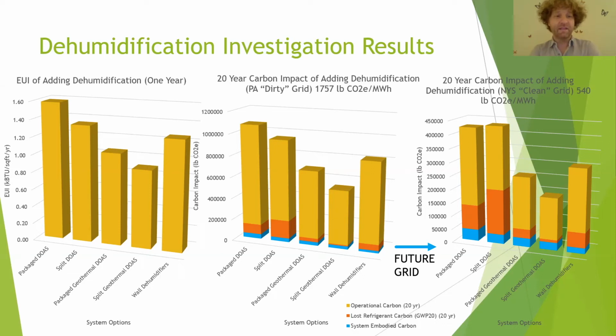On the left is the energy use intensity of adding dehumidification for one year. The packaged dedicated outside air system is decent. The split system is better—in this climate, about 15% better—and most of that energy difference was actually in low temperature performance, none from cooling. It's all in the defrost cycles, because VRF can operate at really low temperatures, whereas packaged dedicated outside air systems can't, so they rely more on electric heat.